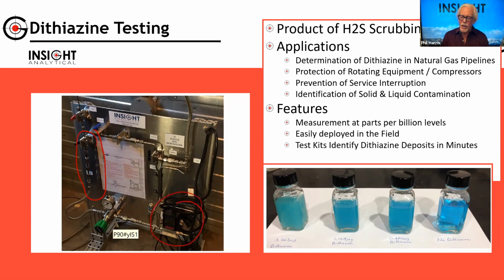We integrate the total flow rate on an integrating flow meter, take the trap out, send it to the lab, and do a lab analysis to say this is how much dithiazine you absorbed when you allowed so many liters of natural gas to flow through the panel. That lets us determine the dithiazine concentration. We've got these installed over a number of parts of the natural gas transmission grid, looking for places where the dithiazine concentration is high, because those are places where we can potentially shut down compressor stations.